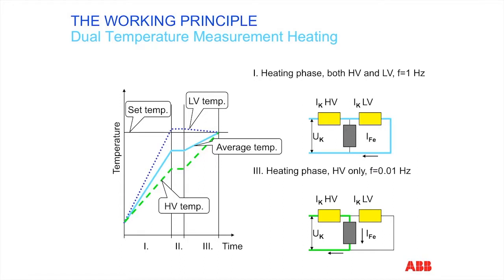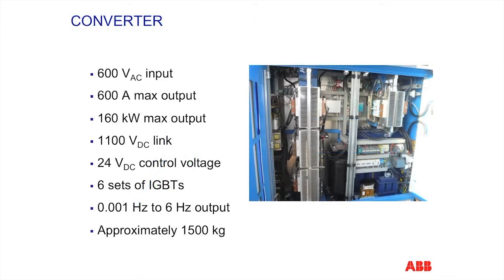As you can see, at 1 Hz, both windings are heated, but at 0.01 Hz, only the HV winding is heated. That frequency is too low to induce a current in the LV windings. Also, you can see the relationship between the HV, LV, and average temperatures in a typical process setting. Here are the input and output values for the converter.